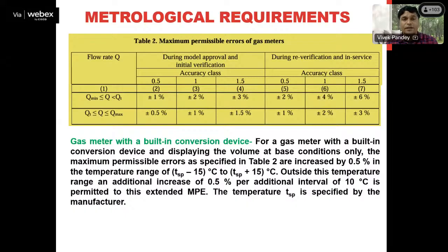So what is the range? If the specified temperature is 30 degrees Celsius, it is 15 degrees Celsius to 45 degrees Celsius. So currently, if the temperature is 25 degrees Celsius, it means it is falling in this range. So it is saying that if the temperature is not equal to the specified temperature, but is lying in this range which is given here, fine, then the MP will become what? 0.5% more than the specified MPs for the gas meter depending upon its accuracy class.